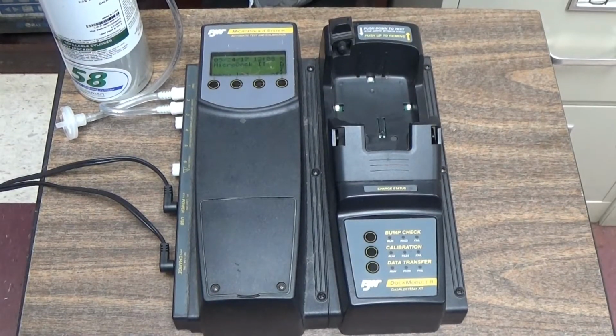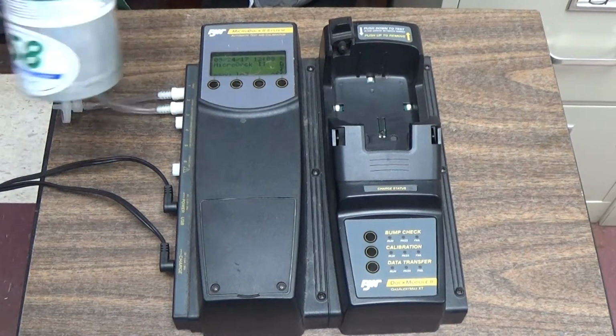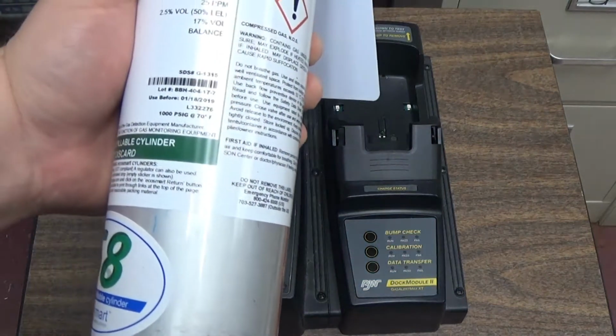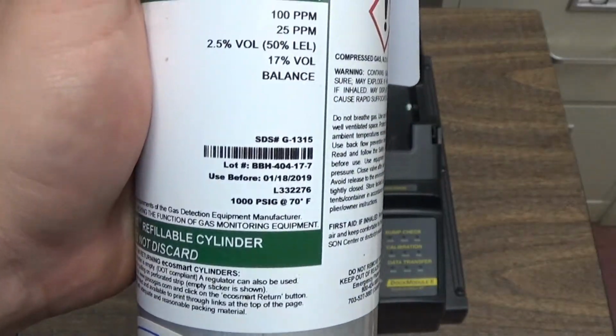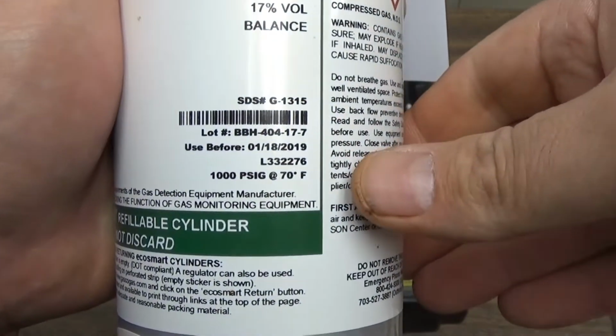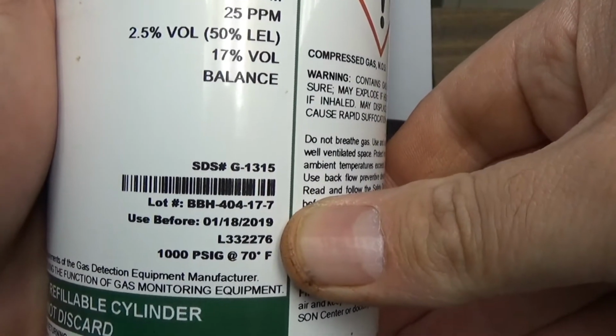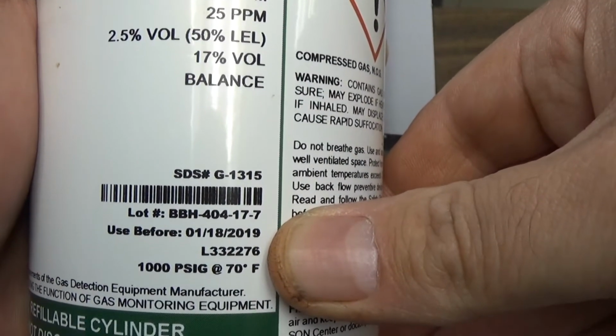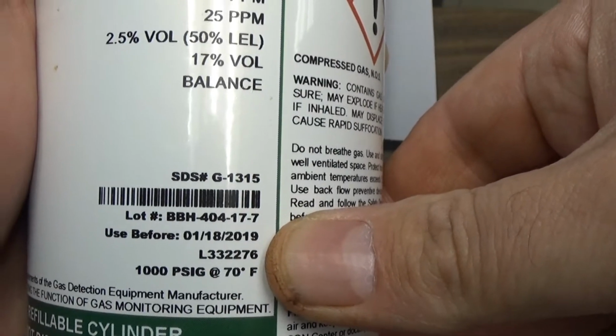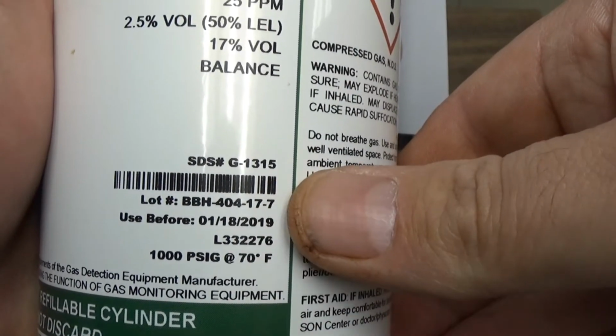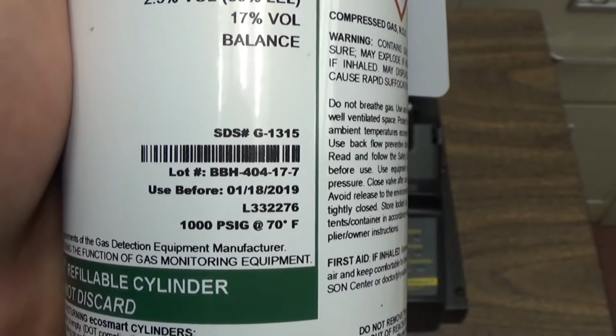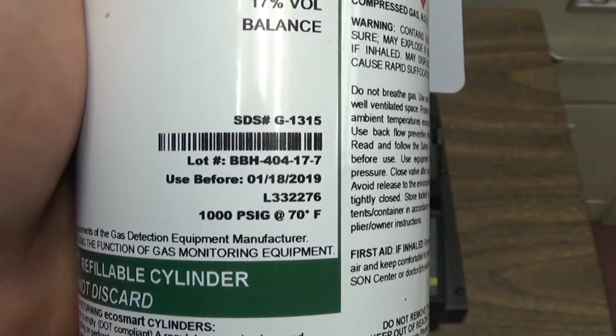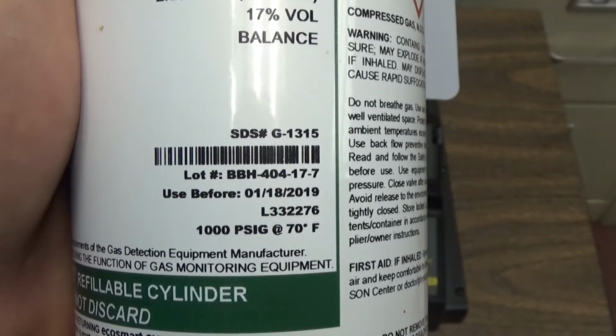Before you begin your bump test or calibration, you always want to look at the lot number and the expiration date on the bottle. On the bottle, you'll see a use before date. You see this is 1/18 of 2019. You'll record this information along with the lot number onto the calibration form found on SAMS.